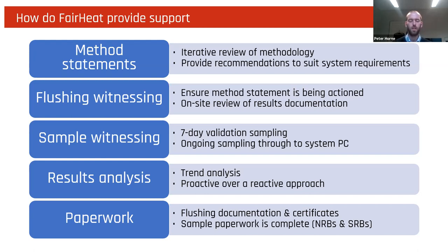So ideally one or two back and forth with the water treatment specialist to make sure that we get all of the guidance and requirements included within that method statement, so that we can then use the method statement as effectively a Bible through the rollout of the process. So we're looking to ensure that flushing velocities and dosing and various on-site documentation are conducted and completed throughout the flushing process.